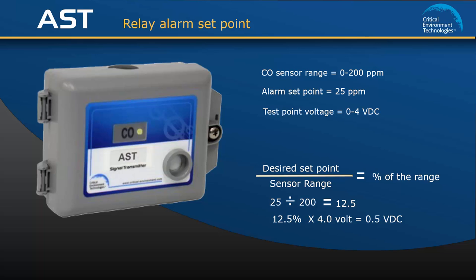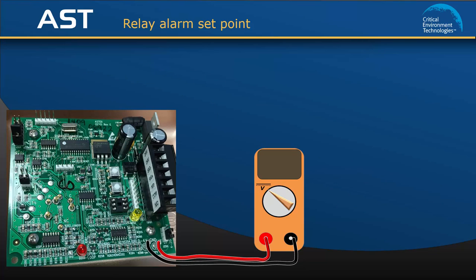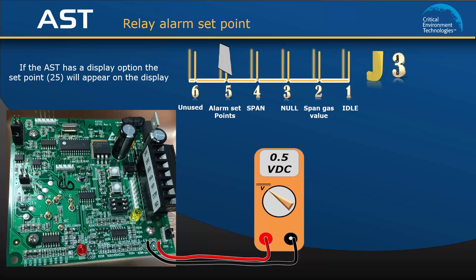To set this alarm set point, attach the voltmeter leads to test points TP1 and TP2. Move the jumper from idle to position 5, alarm set point. The LED will flash green to confirm it is ready for you to set the value. Use the up and down push buttons to adjust the number to the calculated voltage reading on the multimeter, which is 0.5 volts in this exercise. If the AST has the optional display, the display will show 25 ppm. Move the jumper back to the idle position and the alarm set point value will be saved. The LED will flash green once for confirmation.